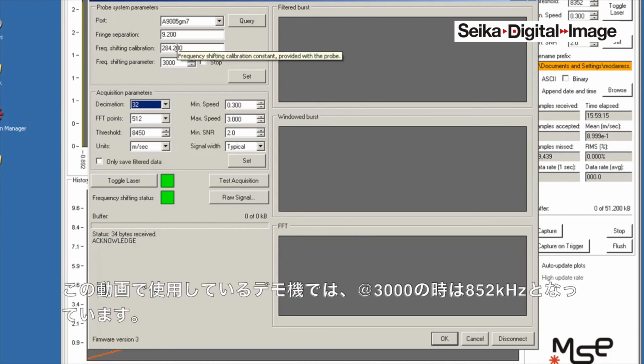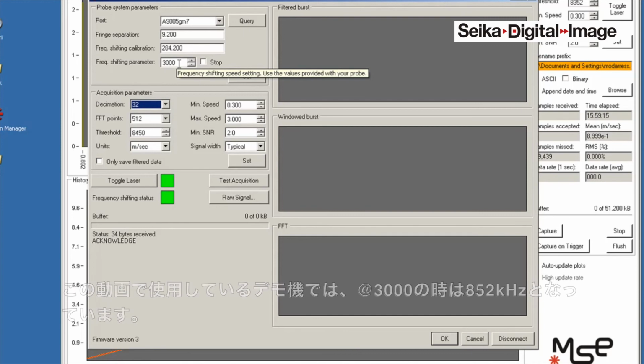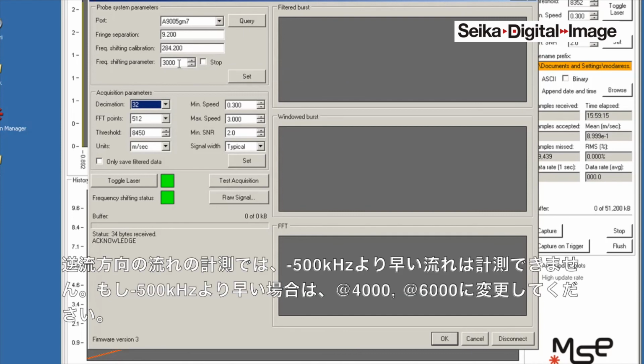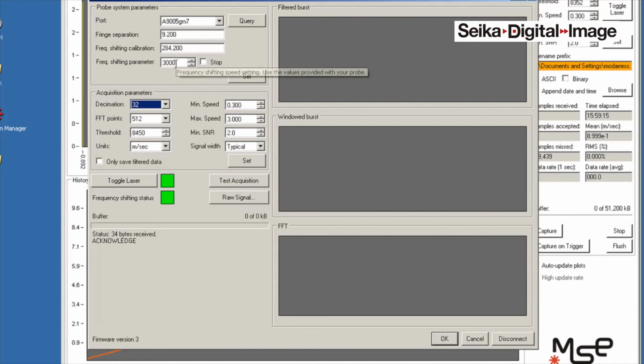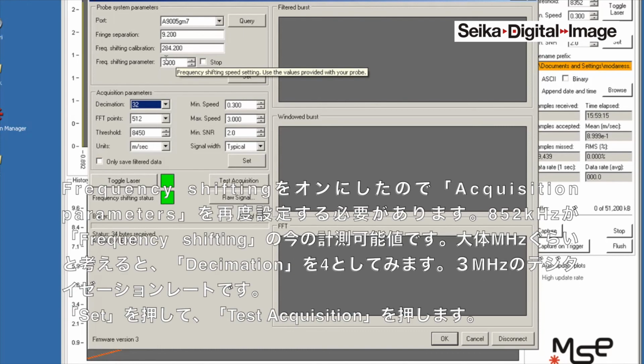For 3000, for this probe, the characterization sheet shows that it has 852 kilohertz frequency shift. And if your negative velocity is not larger than, let's say, minus 500 kilohertz, this is adequate. If the negative velocity is larger, then you need to go to higher frequency shifting. And those are described in the manual.